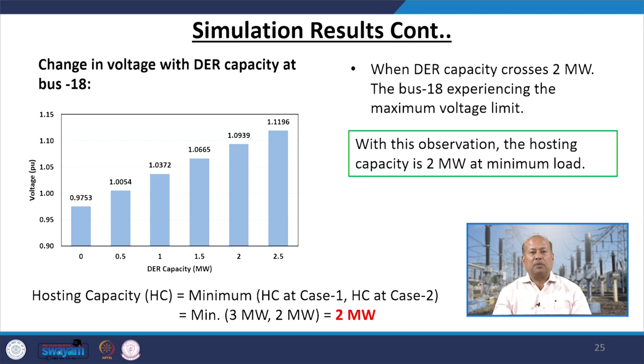So, the conclusion here, as you could see, the moment we go from 0, 0.5, 1, 1.5, 2, it is within limit. The moment you inject 2.5 megawatt, it is violating my 10% limit. So, what does it mean? In the first case, maximum loading condition, we found it is 3 megawatt. In case of minimum load condition, we found it is 2 megawatt. So, the minimum of 3 megawatt and 2 megawatt is 2 megawatt, which means a hosting capacity of 2 megawatt will be acceptable to the system either in maximum loading operational conditions or during minimum loading operational conditions. So, with this observation, the hosting capacity is not 3 megawatt, but it is 2 megawatt at minimum load.